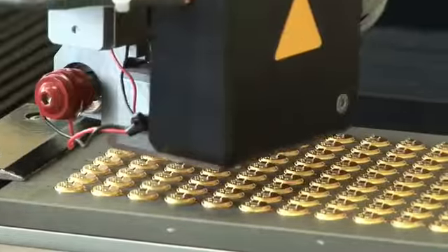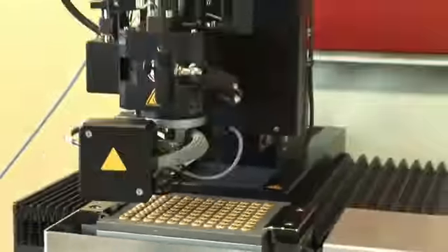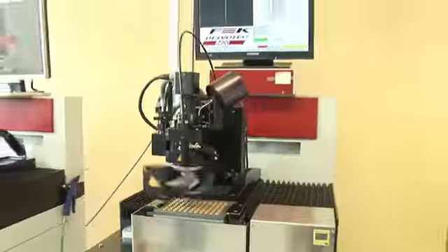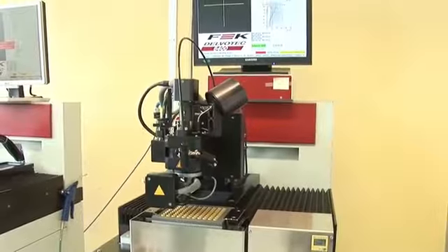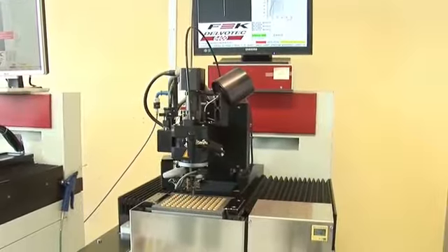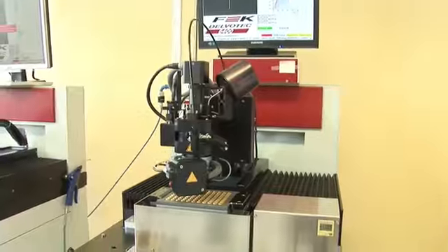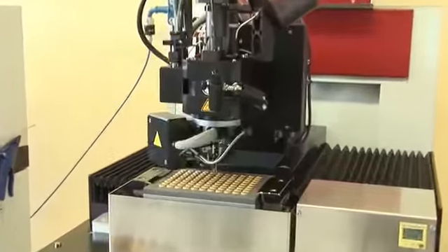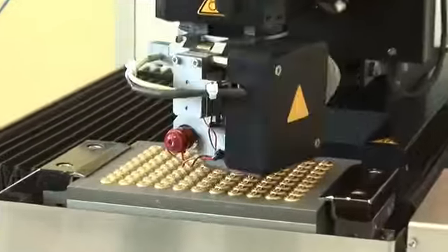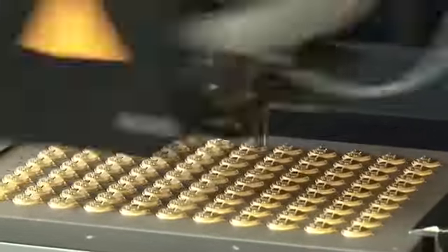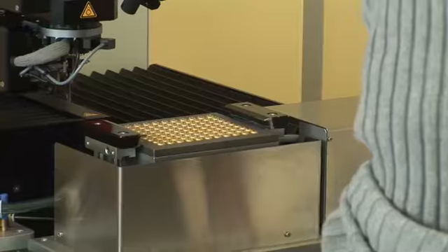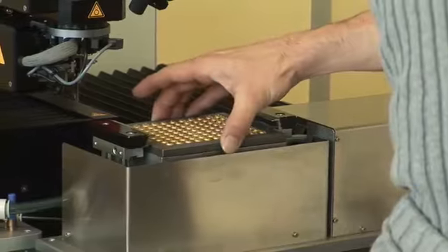The sensor element is now electrically bonded to the base plate. To do this, the signals from the sensor element must be connected to the glass feed-through individually, which typically requires 4 to 5 bonding connections. The delicate bonding wires, which have a diameter of just 30 thousandths of a millimeter, are bonded using special bonding machines that use ultrasound to weld the ultra-thin wires to the glass feed-through.